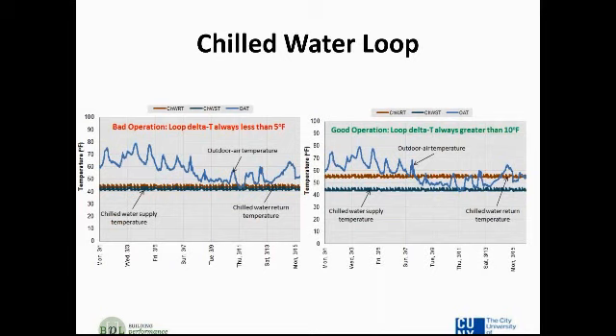We don't like that. Obviously, in order to get good operation out of your chiller, which is a very expensive piece of equipment to run, you would want to have a much larger delta T. Let's make use of all that chilling that we've done. On the right-hand side, you can see that obviously it's a much better delta T, closer to 10 degrees.